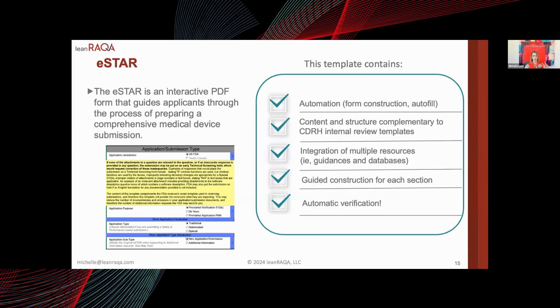Another advantage — though a double-edged sword — is the eSTAR submission system. On one hand, it takes a lot of the guesswork out of assembling a submission for the agency. It has extensive help text to identify the types of information FDA expects, links to guidance documents, and a completeness verification. It also interfaces directly with the internal templates the FDA uses to evaluate the submission.